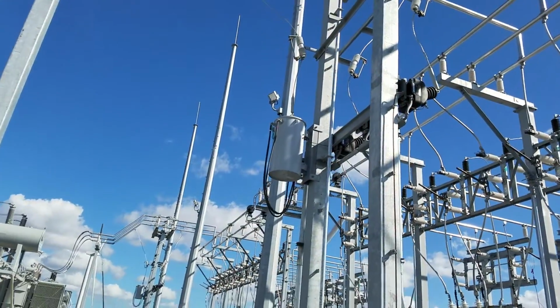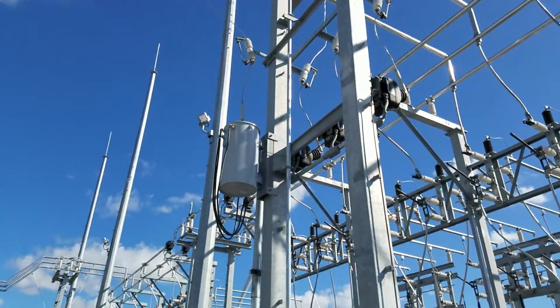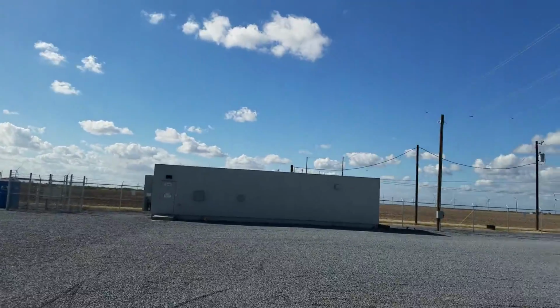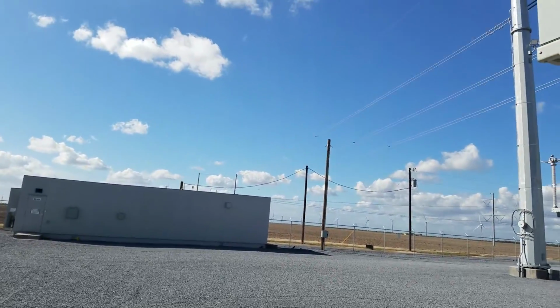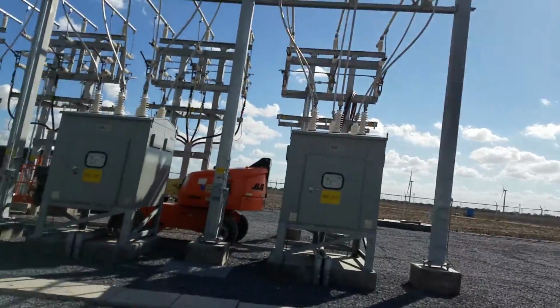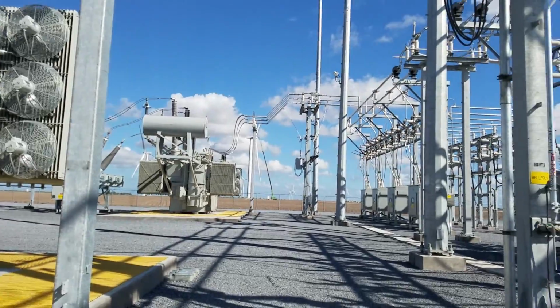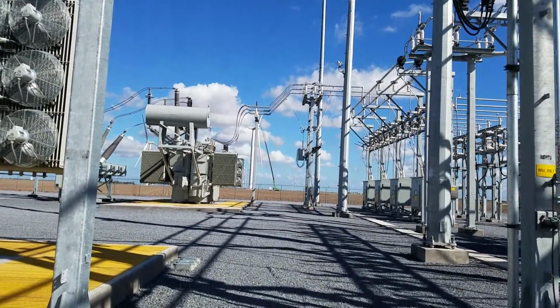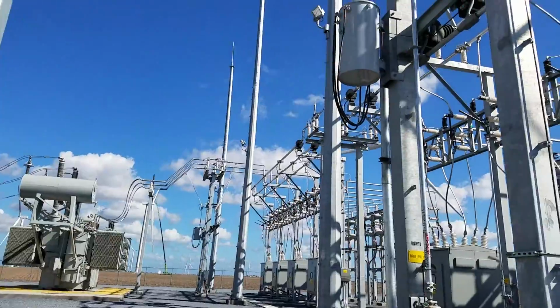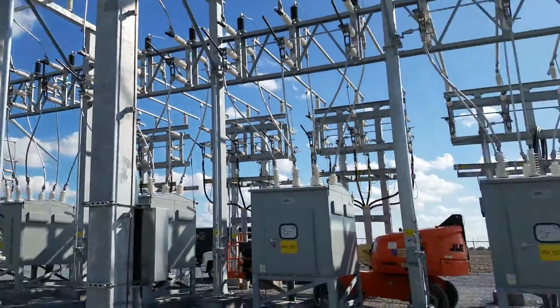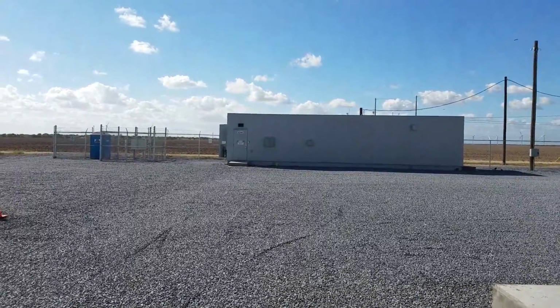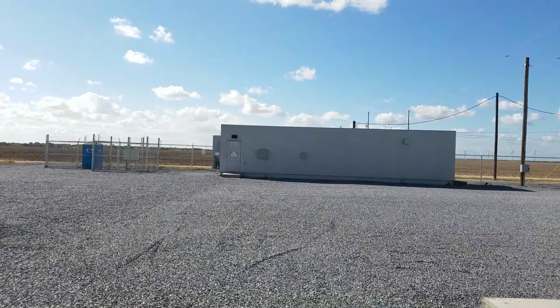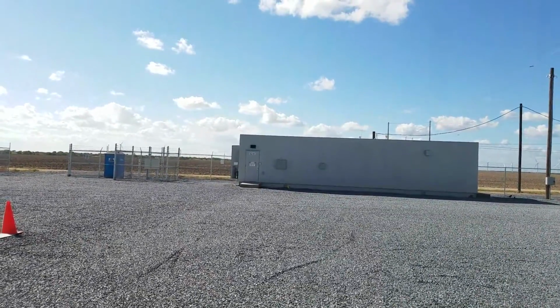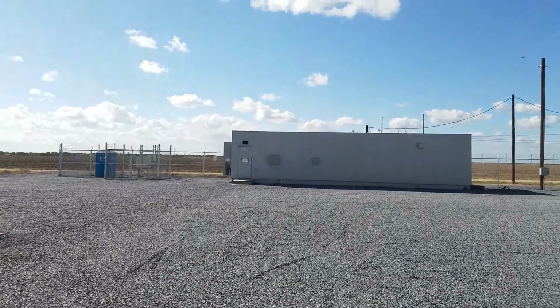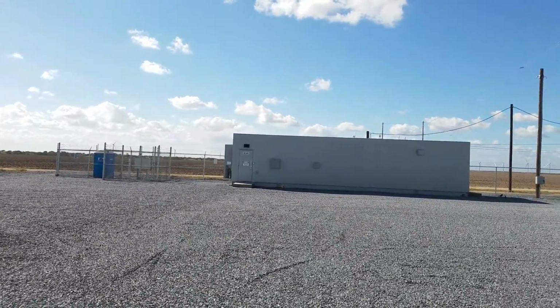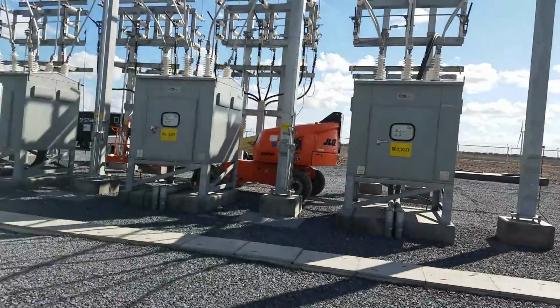That little transformer there, that's a station service transformer. That feeds power into that building there. They also have utility power as another backup. And if you notice on the other bay, they've got one down there as well. So they've got 3 sources of power if needed. Plus, if you see that junction box outside there by the door on the right, or right of the door, and the door's on the left, that's for hooking up a generator.